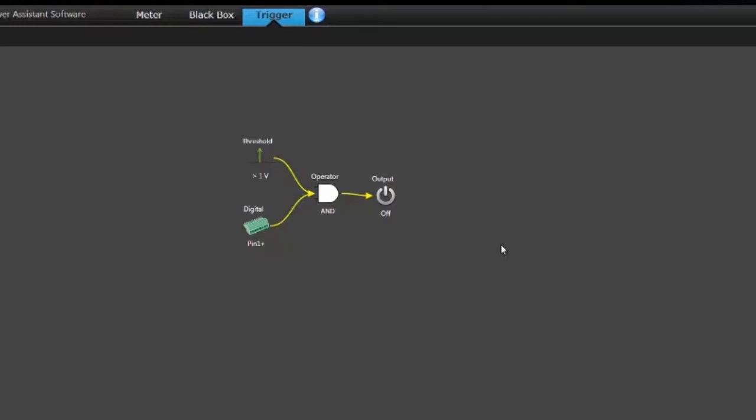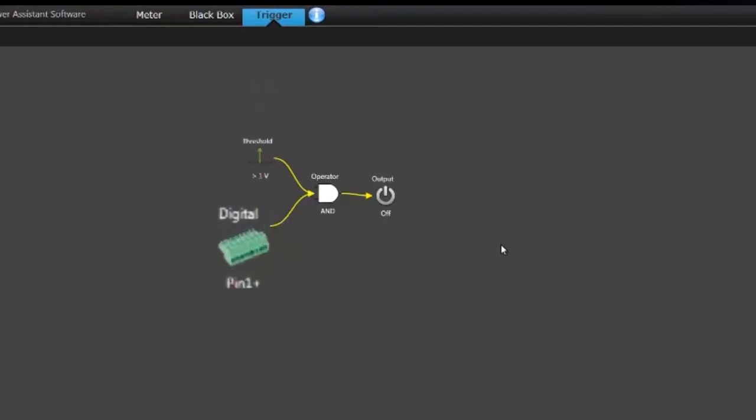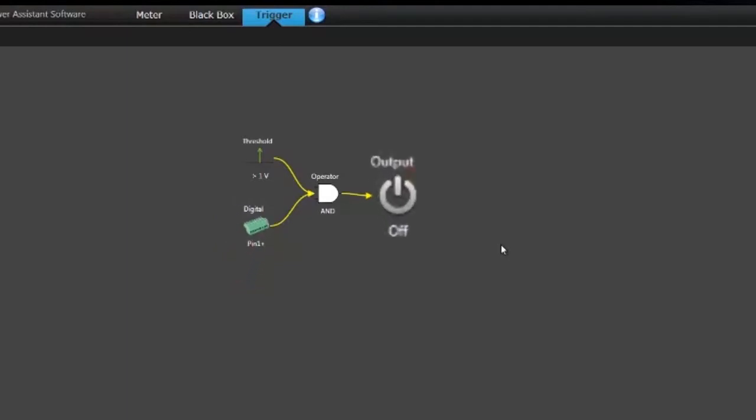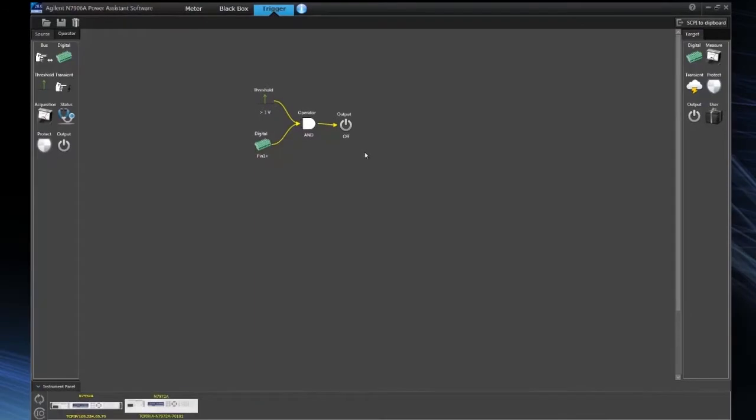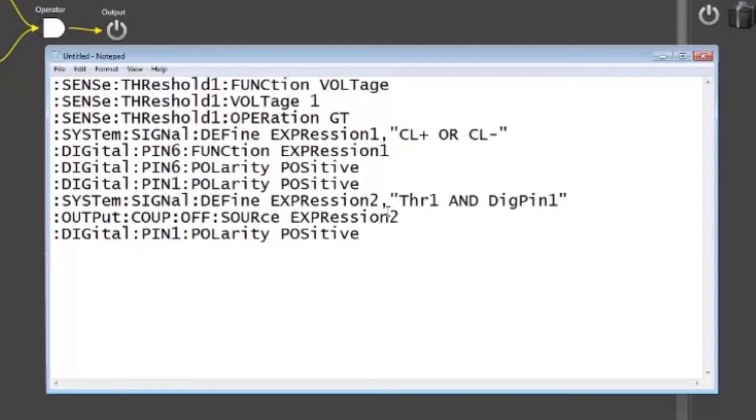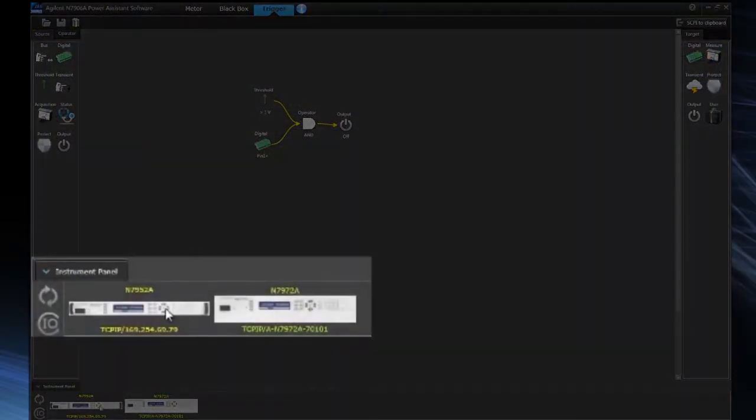Now what I've just done is I've created a trigger condition where if the threshold goes above 1 volt and I get an input on the digital input pin 1, I will then shut off the output. So what I can now do with this trigger configuration is I can get the SCPI commands and easily paste them into my programs. So here's all the SCPI commands it takes to create that logical trigger expression I just built graphically in the software.